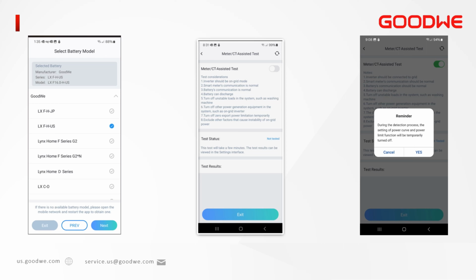Now you're going to be on the battery models. Here the inverter will automatically detect the battery connected. As you see on the screen, it automatically recognizes our Lynx FH batteries. If you're getting to this step and the inverter doesn't automatically recognize the batteries from the list, you need to troubleshoot the batteries. First, start by checking if the battery breaker is closed.